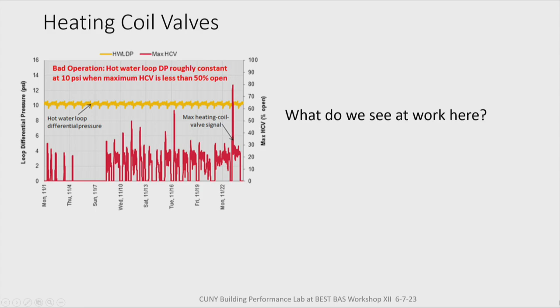Anytime we see a highly throttled device, be it a valve or a damper, we think there might be an opportunity there. Let's go to the next slide, which just shows bad operation—in other words, the valves are very highly throttled, and we're working at an excess of unnecessarily high pressure in the loop.